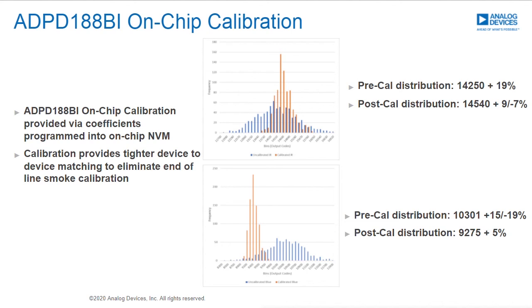Because if you know that every part is going to be within 10% of the previous part, you can do a characterization while you're developing your smoke detector and be able to eliminate this last step calibration with an actual smoke source and still guarantee that everything is going to be within 10%. And the UL limits are 25% margin, so the 10% is well within that margin.